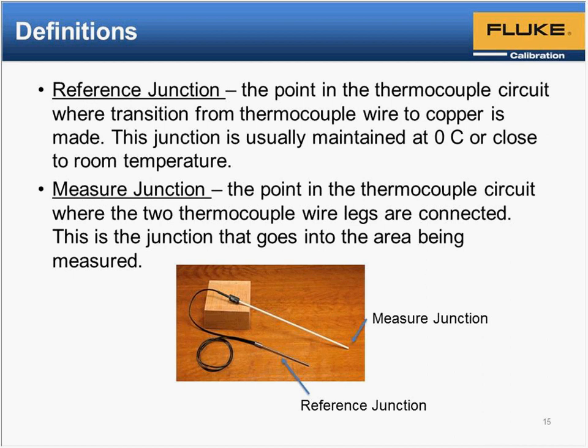Essentially, like the Fluke 8846A. I have to admit I haven't looked at the specs on that, but it would probably be fine for base metal thermocouples. I don't think it has any voltage-to-temperature thermocouple conversion. Now I'm more familiar with the Fluke Hart products, like the Black Stack instruments, the 1586A. The 1586A is kind of nice because it's similar to a DVM in that it measures thermocouples, and it also measures PRTs and thermistors. So you have a variety of options. But anyway, those are my recommendations.